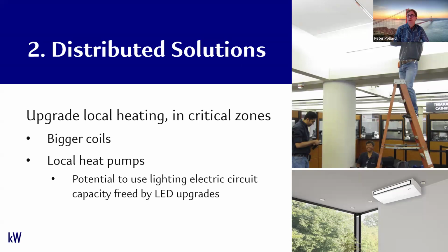The classic one is to install bigger coils. Coils are basically radiators—that's where heat from the hot water gets distributed into a space. Putting bigger coils throughout a building is a very invasive and expensive project. You can do it, and practically, if it's a gut rehab situation, that's the classic way to do it. In a new building, you just build it that way from the start—go ahead, build it all electric, no problem, with radiant heating that can handle heat pump temperatures. But for existing buildings, we again focus on critical zones, where you can install bigger coils.